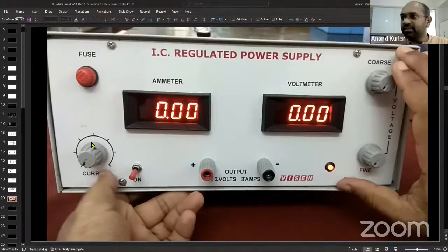So this is the current knob. Make sure, very important, calibrating voltmeters is very easy. Anytime you connect an ammeter where current is involved, be very careful. If you pass 12 volts through your 0 to 1 ampere meter, you'll blow it in no time. So before you connect anything, make sure this current knob is all the way down to 0. You connect this and slowly increase the voltage to 3 volts and keep this at exactly 3.00.